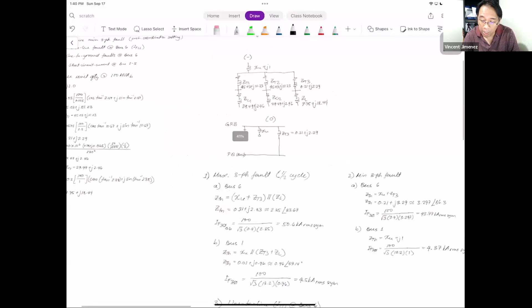Okay, objective number 2. Line-to-line fault at bus 6. This is just simply computed, and it will also be used for the protection setting, because your transformer is delta-Y, so the line-to-line value is important. You use the 3-phase fault at bus 6 as the minimum.